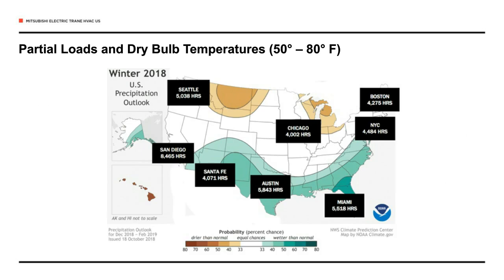So this shows the number of bin hours in some of the major cities shown. For example, Chicago has about 4,000 hours between the ambient temperatures of 50 degrees and 80 degrees Fahrenheit. So we have to size our systems, both for heating and cooling, for our worst case winter day and our worst case summer day. However, we operate at those points less than 1% of the time. This is really where we're operating most of the time. So we want to make sure that the system is energy efficient at these points. And that's where VRF system shines, is at part load. And we can see there's a lot of part load hours even in colder climate cities such as Chicago.